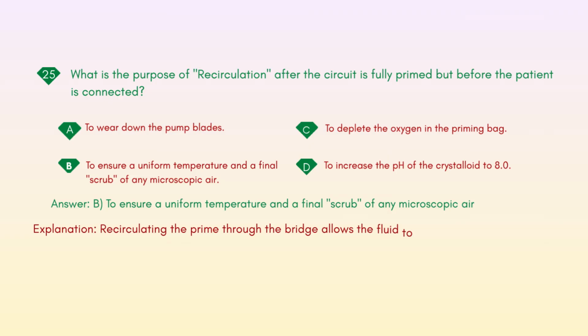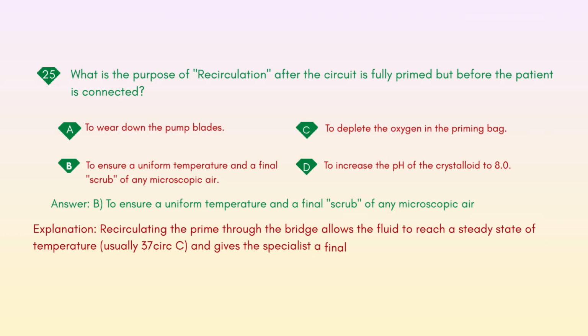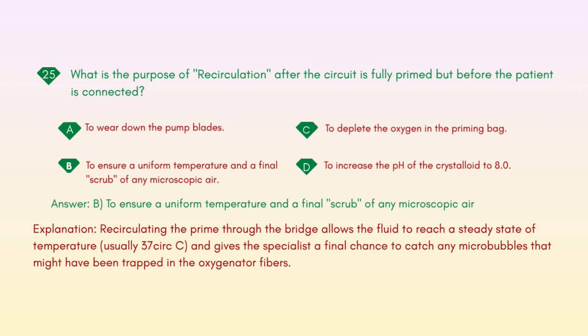Explanation: recirculating the prime through the bridge allows the fluid to reach a steady state of temperature, usually 37°C, and gives the specialist a final chance to catch any microbubbles that might have been trapped in the oxygenator fibers.